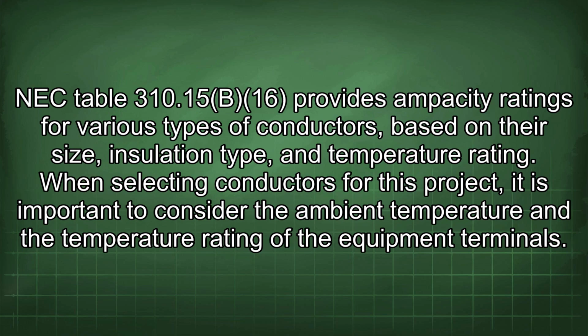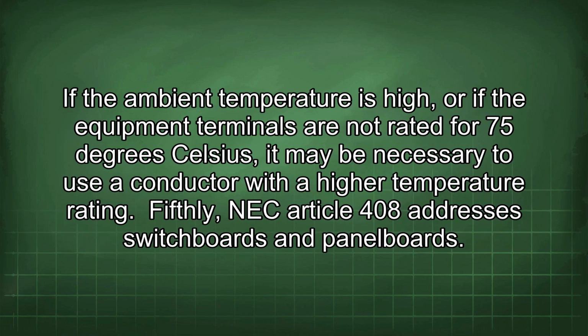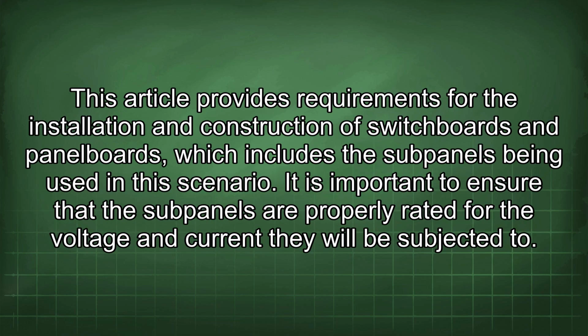When selecting conductors for this project, it is important to consider the ambient temperature and the temperature rating of the equipment terminals. If the ambient temperature is high, or if the equipment terminals are not rated for 75 degrees Celsius, it may be necessary to use a conductor with a higher temperature rating. Fifthly, NEC Article 408 addresses switchboards and panel boards. This article provides requirements for the installation and construction of switchboards and panel boards, which includes the subpanels being used in this scenario.